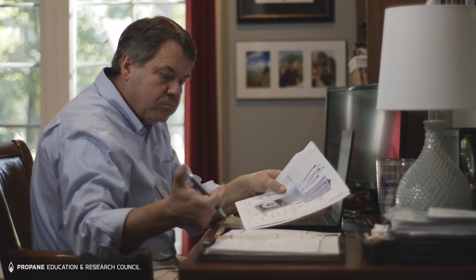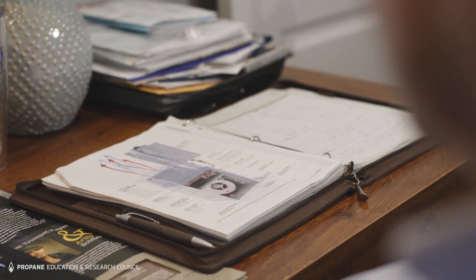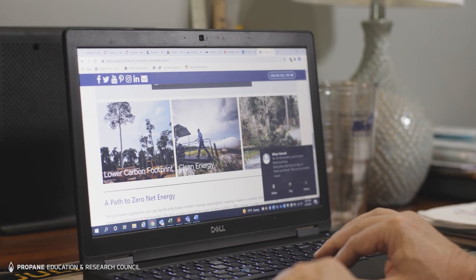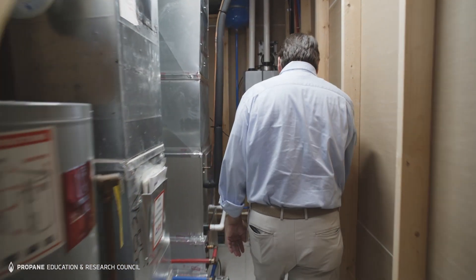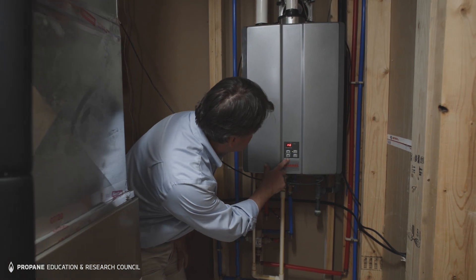What inspires me about the technology first and foremost is the comfort. A heat pump will deliver register air temperatures of somewhere around 95 degrees at best, where a gas furnace will deliver approximately 140 degrees register temperature. In consulting with Rinnai, they felt I'd realize approximately 130 degrees register temperature, and that's about what it came out to be after installation.